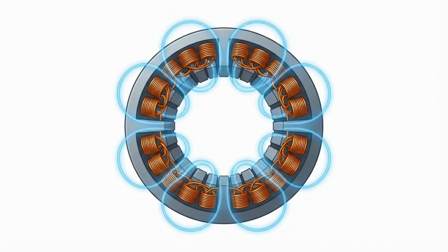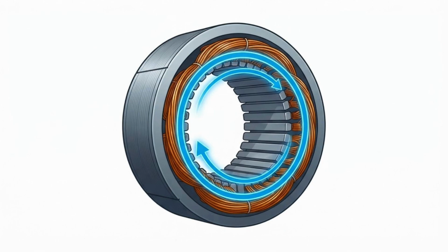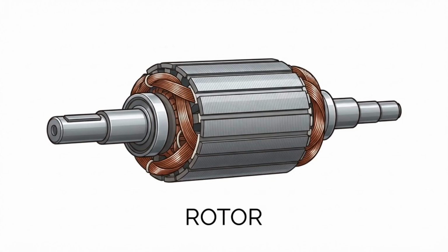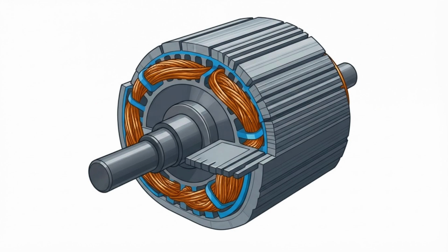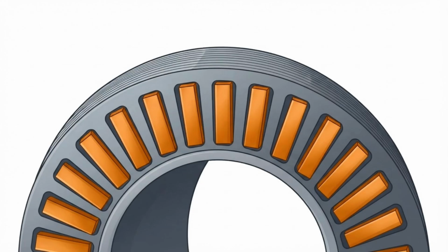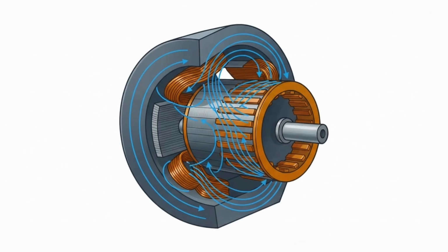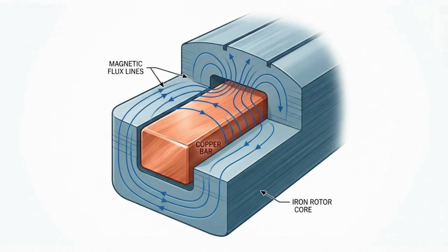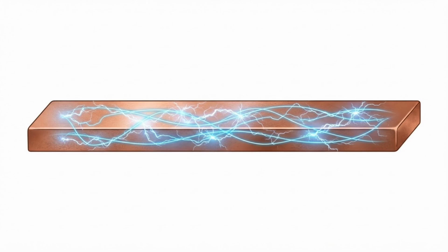When the synthesized alternating current from the inverter surges through these coils, it generates an invisible, incredibly powerful magnetic field that rotates rapidly around the inside of the motor. The spinning inner shaft, or rotor, is constructed of stacked iron plates embedded with thick copper bars.